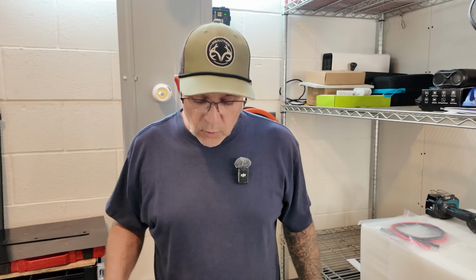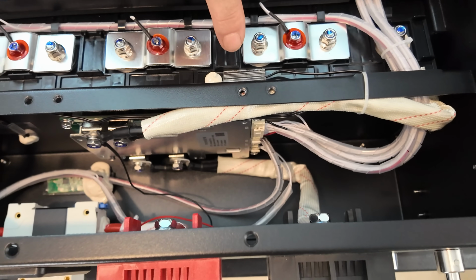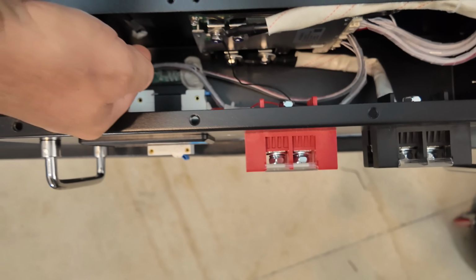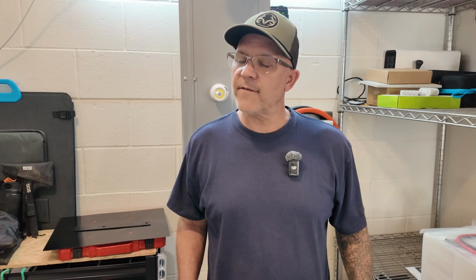One of the biggest risks with these batteries is overheating, especially with heavy loads or in a hot place without great ventilation. That's why this BMS includes temperature sensors tucked right inside—one on top, and one in the front cavity. It protects you from overheating and from operating in temperatures that are too cold. These constantly monitor the internal heat, and if it gets too hot, it shuts the system down automatically to prevent thermal runaway or permanent damage.